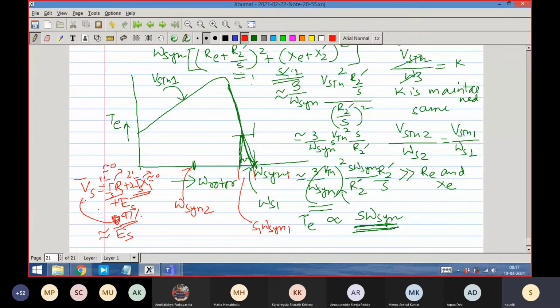Because we have not designed for saturation, now a lot of extra current will go. Saturation means the machine is becoming like demagnetized, like air. From the BH curve, you will see that for more flux, more magnetizing current has to go, because now you are trying to magnetize air.